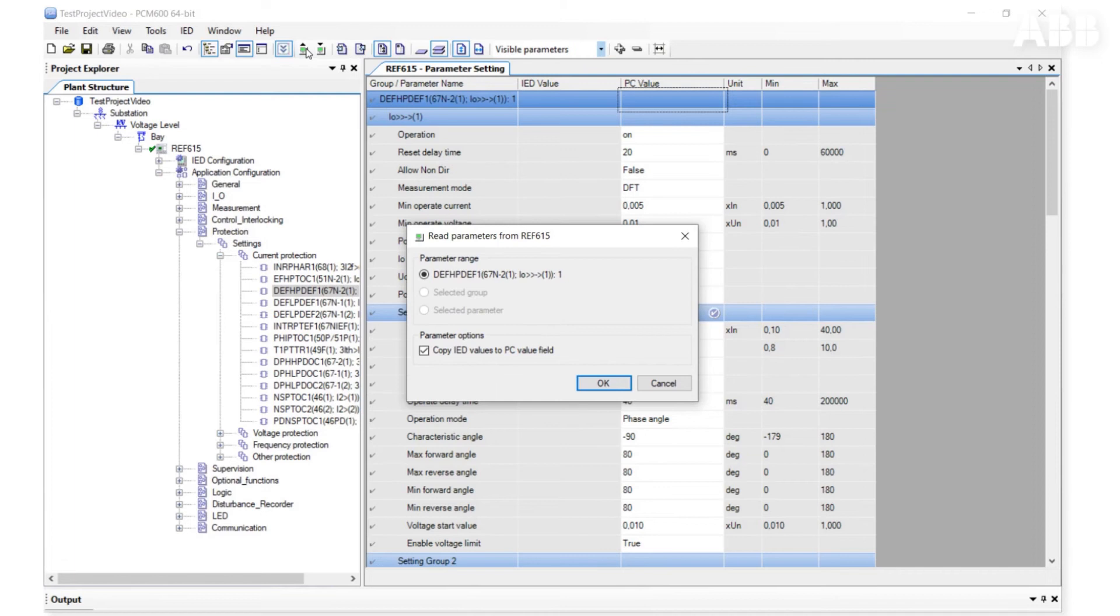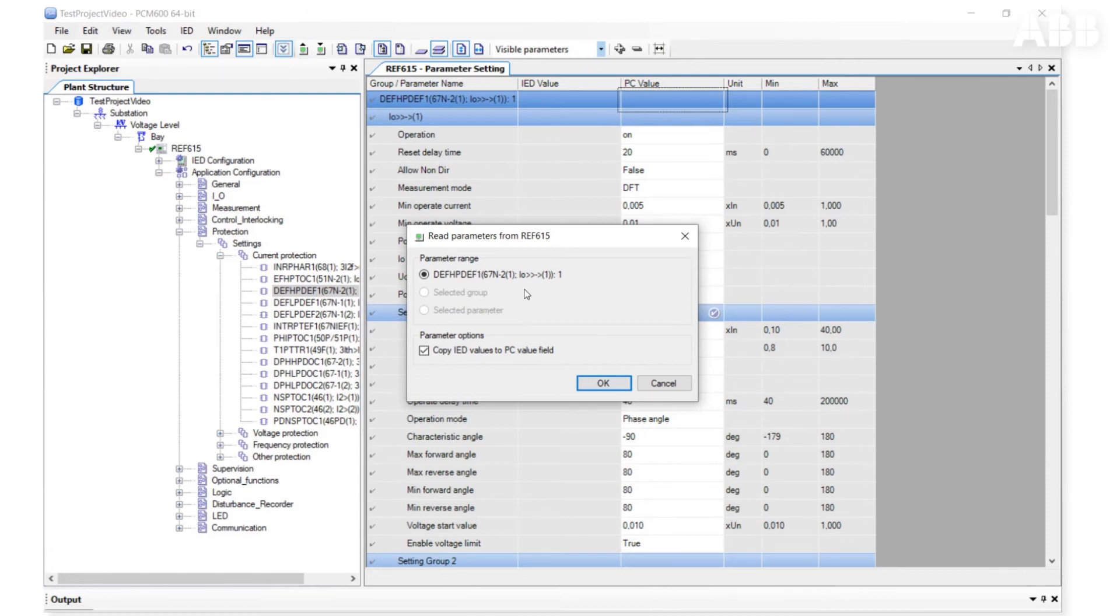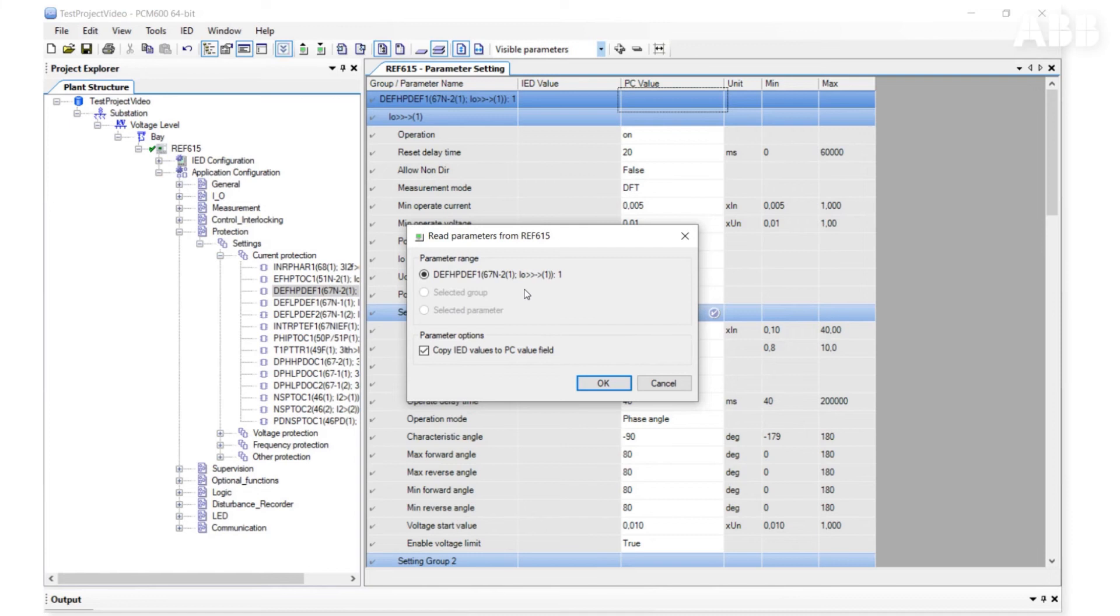By default, the Copy IED Values to PC Value Field option is selected. It means that when we read parameters, we replace all the parameters we have in PCM600 with the ones from the relay. If you just want to read parameters to check or compare them with the parameters in PCM600 while leaving the original PC values, you can uncheck this option.